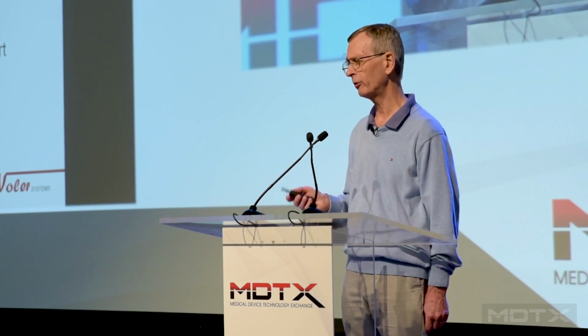Now, a lot of devices people want to put on the wrist. Thoracic impedance can theoretically be measured if you have a device on one wrist and you touch it with the other hand. Now you're measuring impedance through the arms and through the chest. Unfortunately, the arms get in the way. They make the impedance much harder to measure, and it hasn't been accurately done yet. You can measure the breathing rate some of the time with that technology.